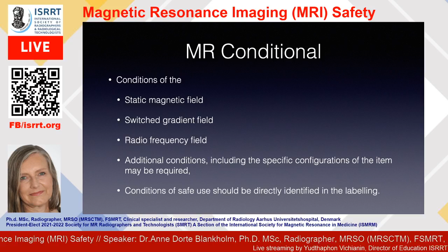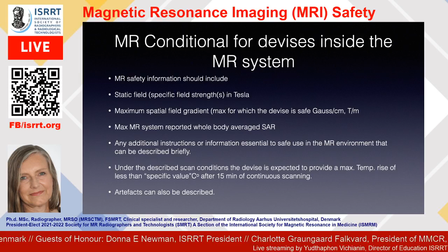And the MR safety information should include the field strength of the static magnetic field in Teslas, the maximum spatial gradient field in Gauss per centimeter or Tesla per meter, and the maximum MR system reported whole body average SAR. And any additional instructions or information essential to safe use in the MR environment can be described briefly. Under the described scan conditions, the device is expected to provide a maximum temperature rise of less than a specific given value in degrees centigrade after 15 minutes of continuous scanning. And we can also see artifacts, the extent of artifacts being described sometimes.